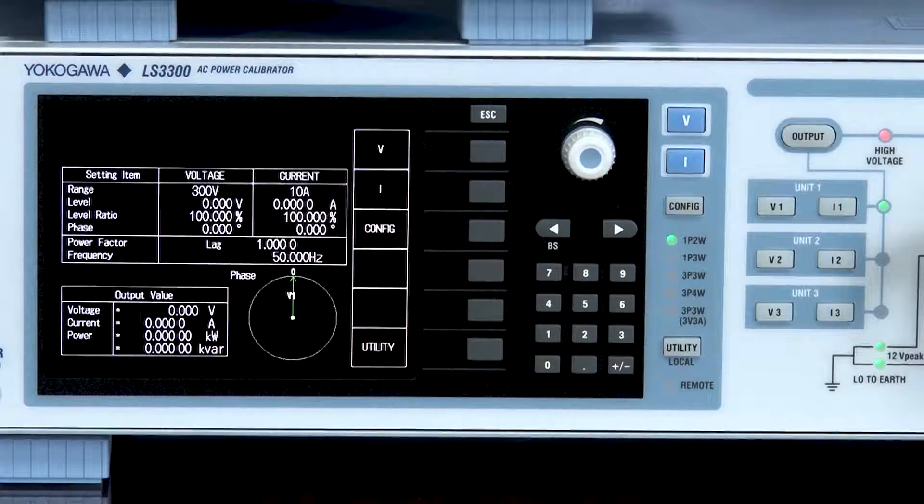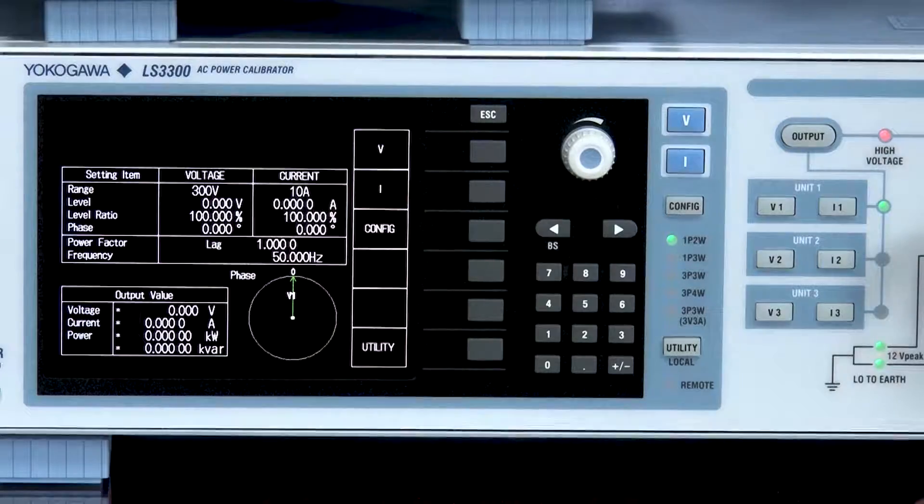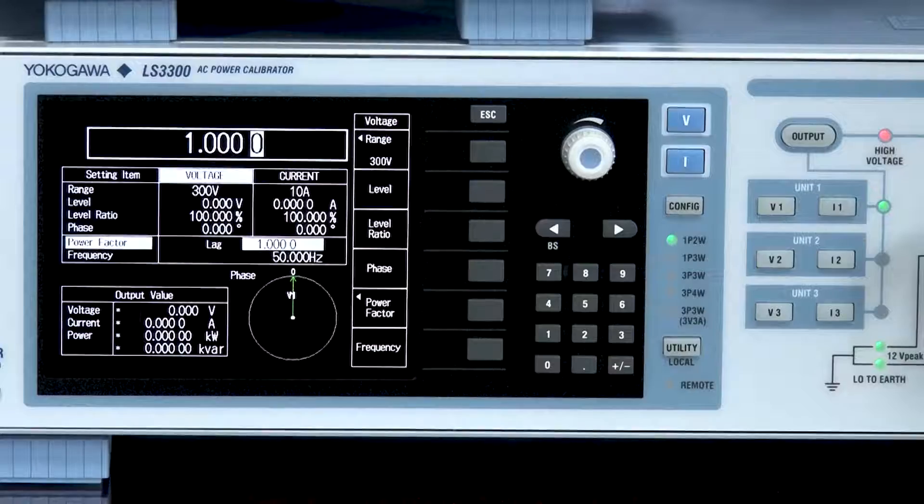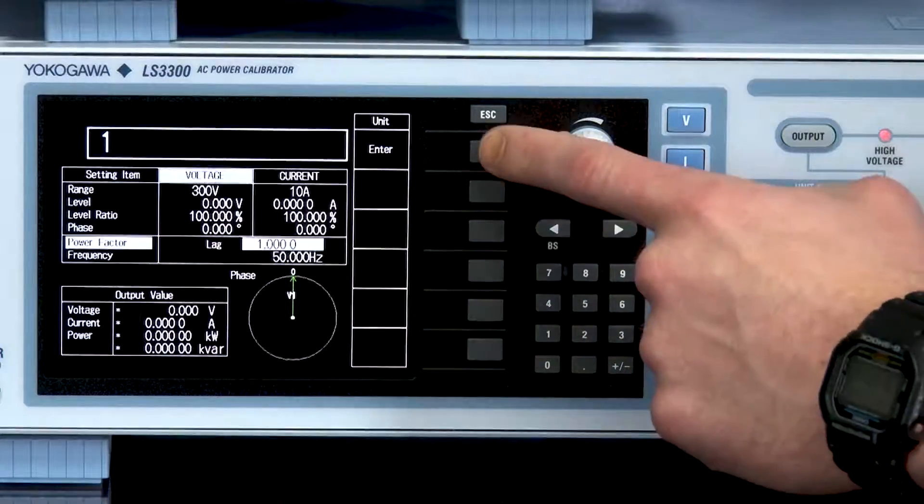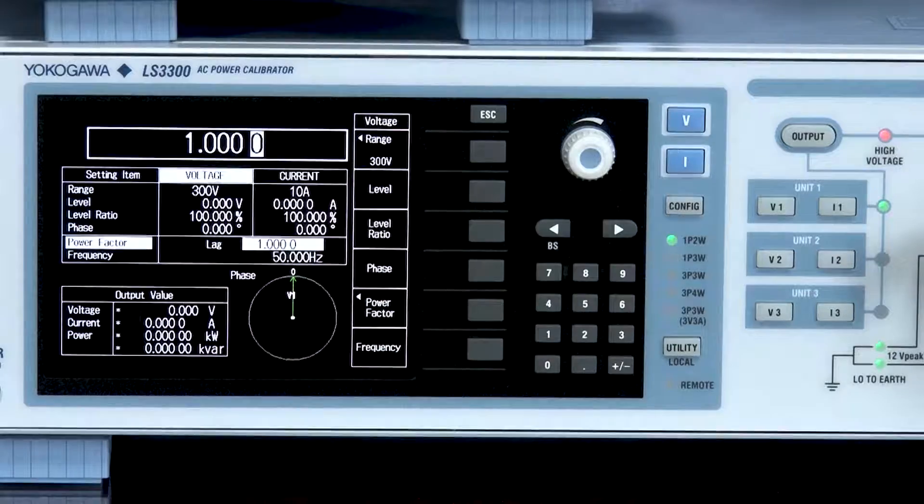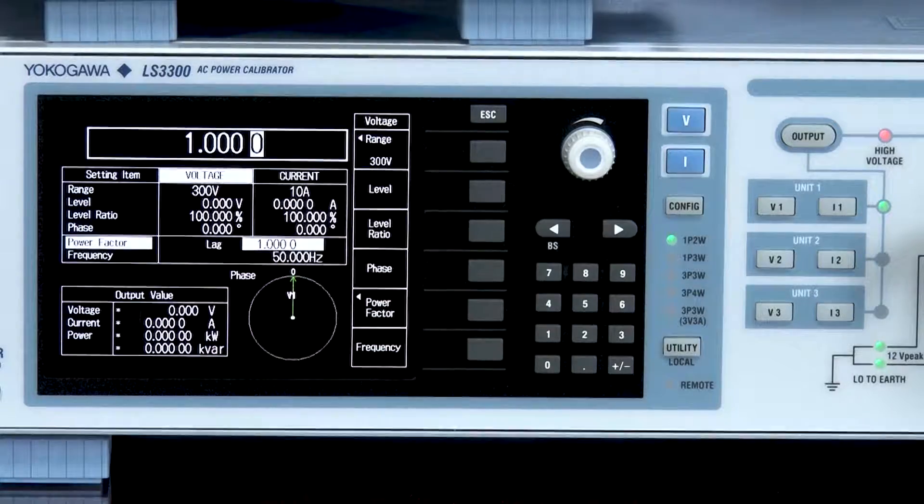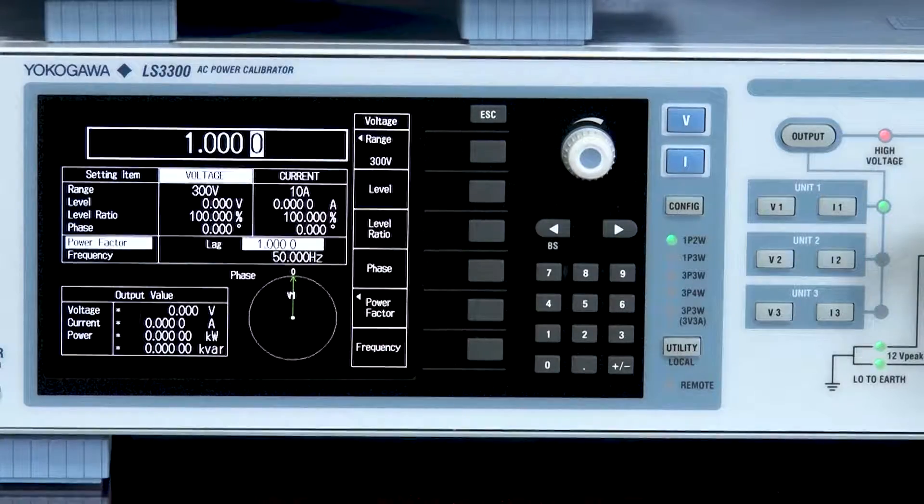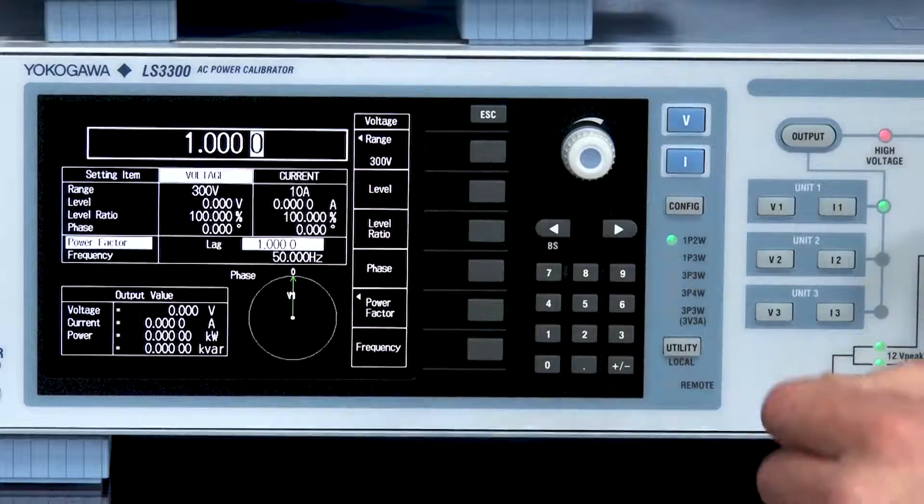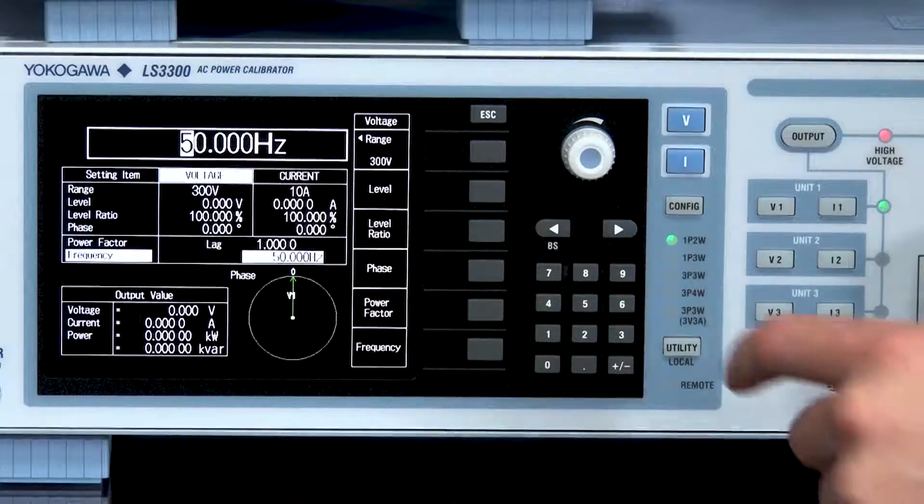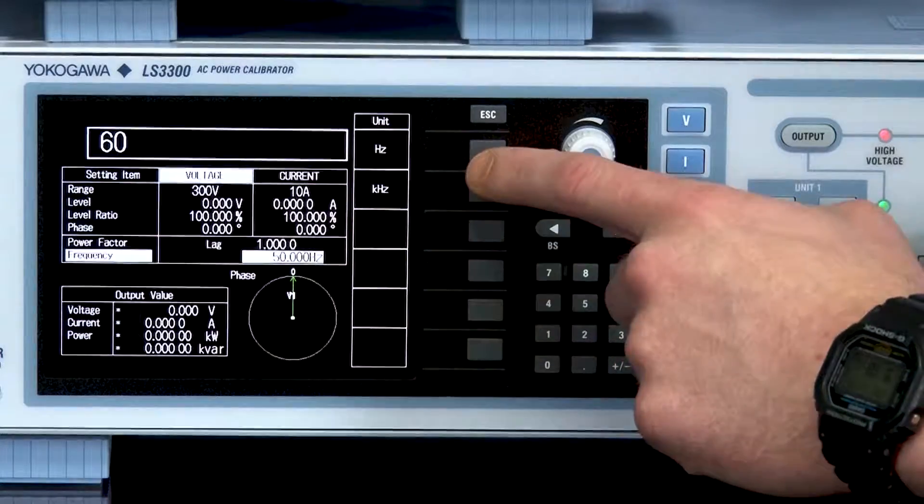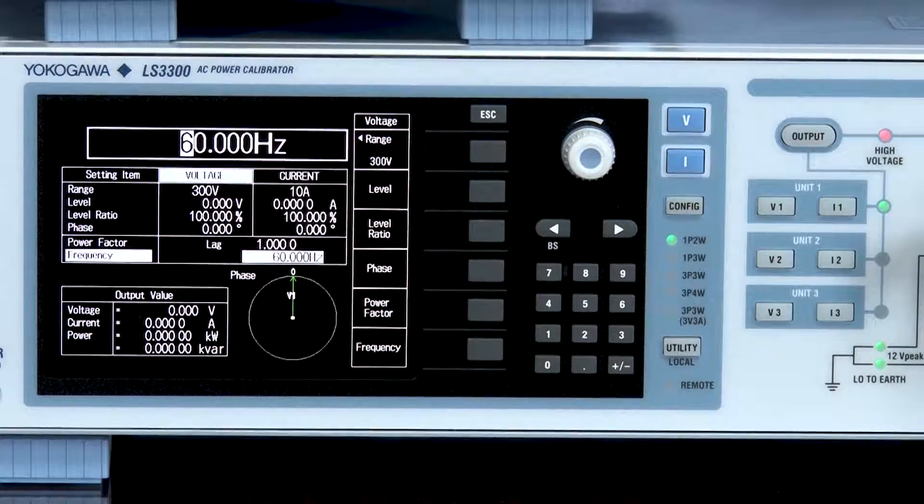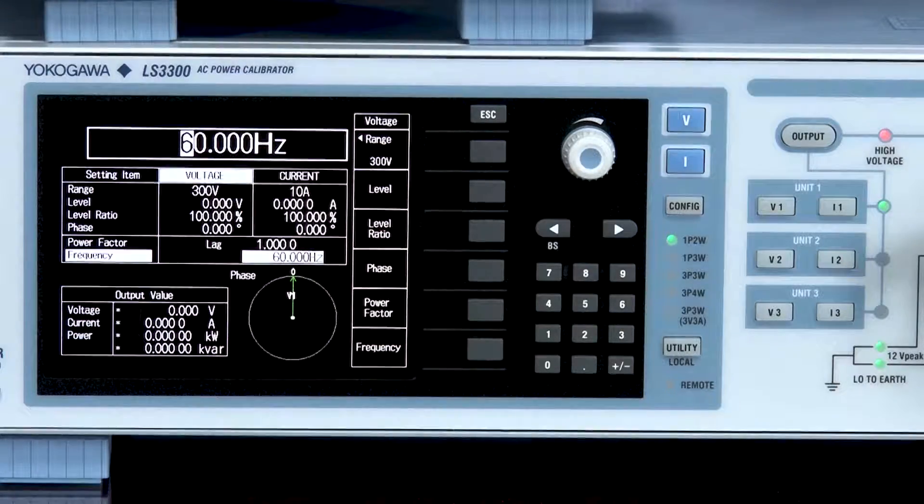Finally I'll set the power factor to one by pressing the soft key next to the power factor. This can be found in the voltage or current menu followed by power factor, enter in your value, pressing enter. The LS3300 allows for the power factor to be set from negative one to zero to positive one. We will also set the frequency during this time by going into voltage or current, selecting frequency, and entering in 60 Hertz for this test. This instrument allows for phase angle to be selected from zero to 359.99 degrees.